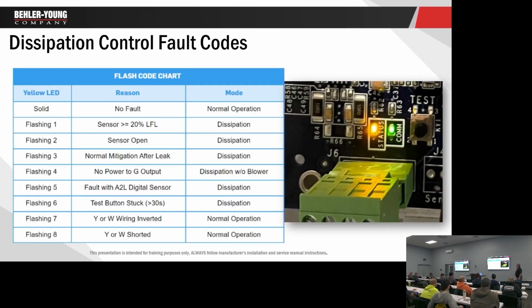Okay. So, the little status light. So here's the codes. Solid is good. A solid light is always a good sign, right? When we talk about the rooftop units later on, solid light's good. We like solid lights. If it's blinking, it means something happened. So if it gives one flash, it's exceeded that 20%, it's mitigating. Second flash, the sensor failed. So if you get a bad sensor, it's going to tell you, and it's going to put it into mitigation. So your customer calls you and says, the blower keeps running on that unit down there. That means it either mitigated or possibly we got a board or a sensor failure. We'd go out there and check it. So that's what would happen.